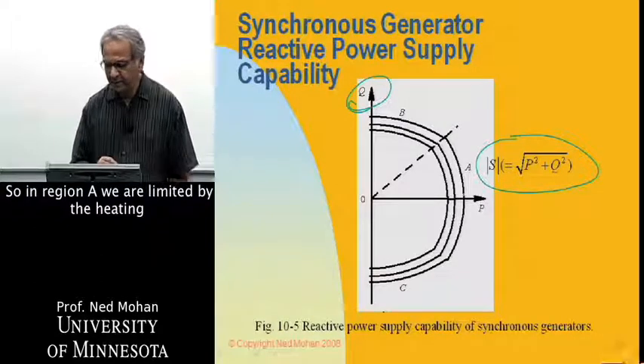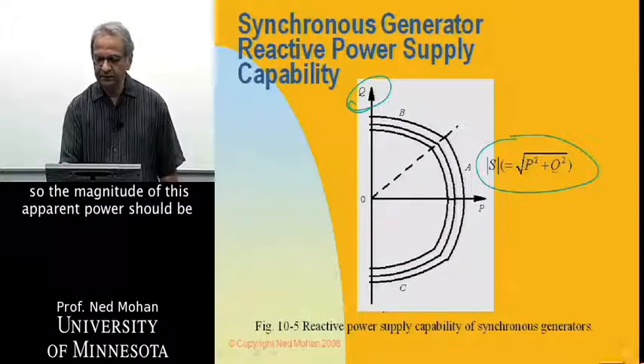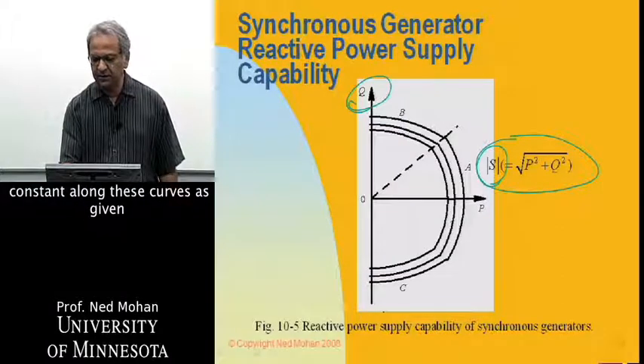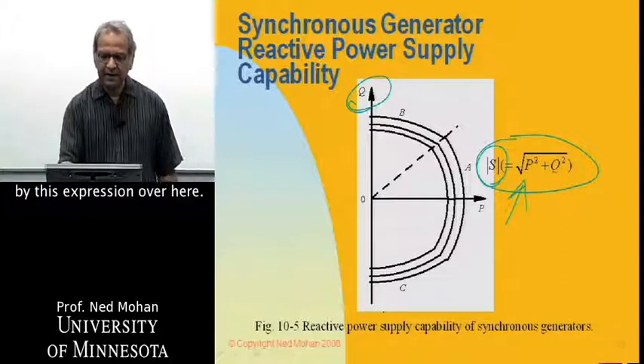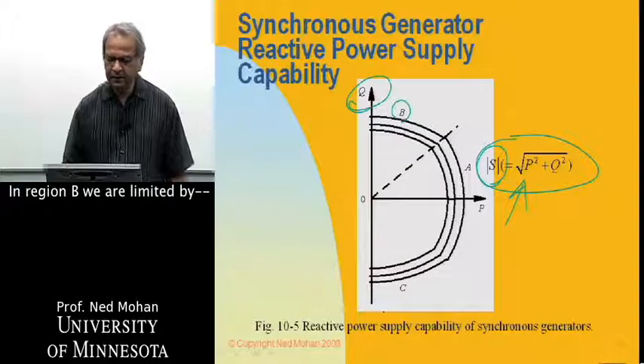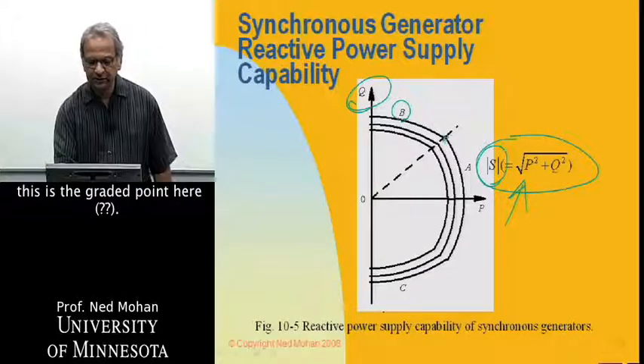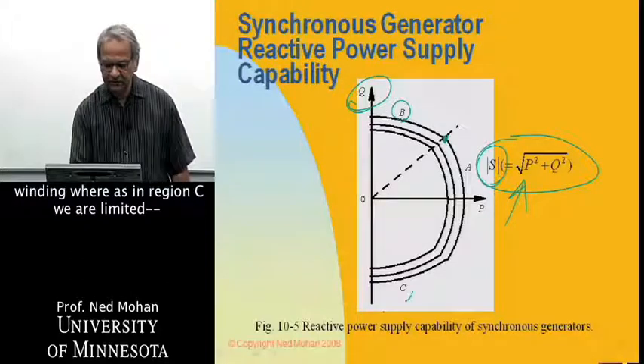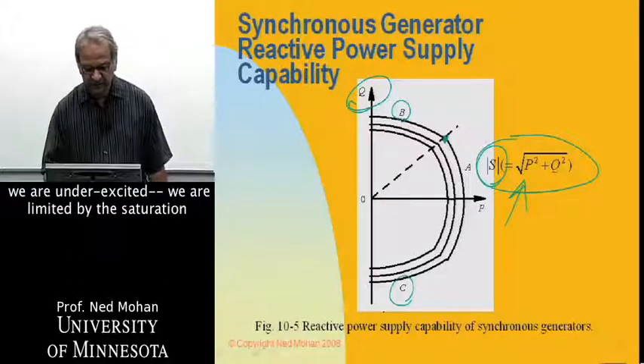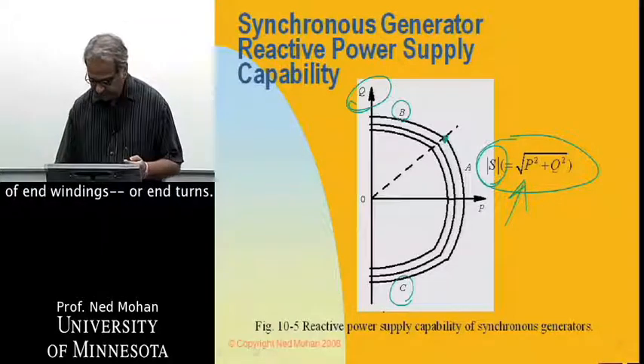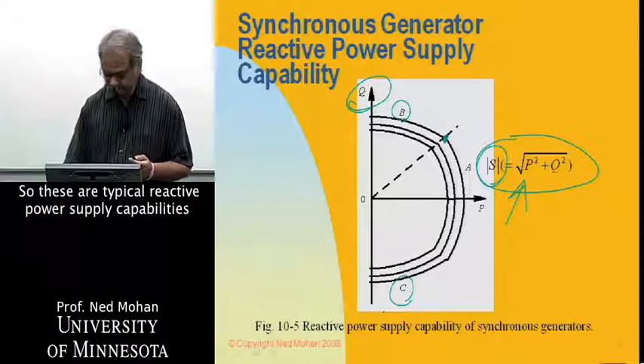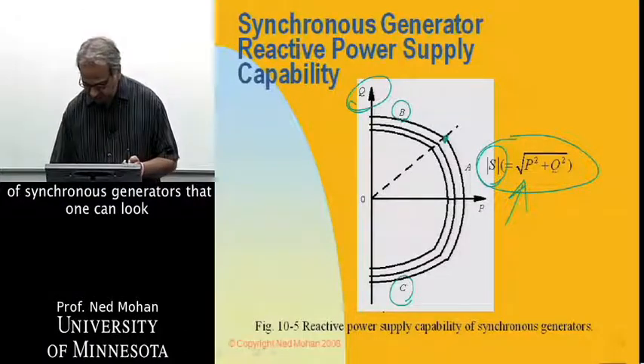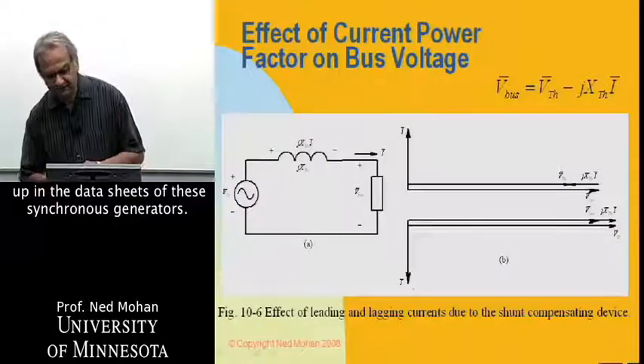In region A, we are limited by the heating of the windings, so the magnitude of the apparent power should be constant along these curves as given by this expression. In region B, this is sort of the rated point, and we are limited by the overheating of the field winding. In region C, where we are very under-excited, we are limited by the saturation of end windings or end turns. These are typical reactive power supply capabilities of synchronous generators that one can look up in their data sheets.